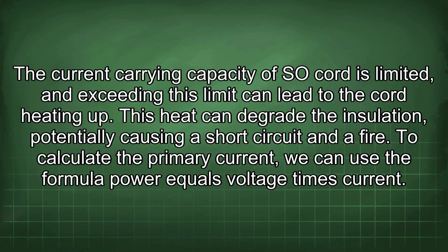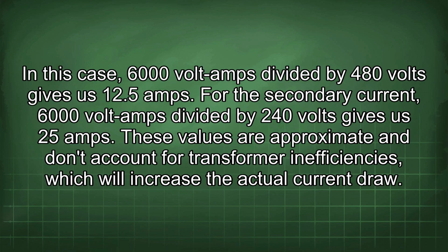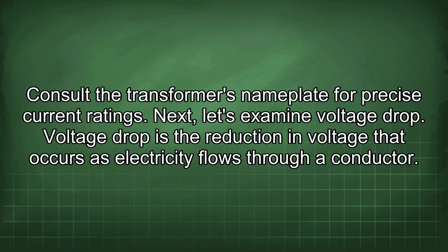To calculate the primary current, we can use the formula power equals voltage times current. In this case, 6000 volt amps divided by 480 volts gives us 12.5 amps. For the secondary current, 6000 volt amps divided by 240 volts gives us 25 amps. These values are approximate and don't account for transformer inefficiencies, which will increase the actual current draw. Consult the transformer's nameplate for precise current ratings.